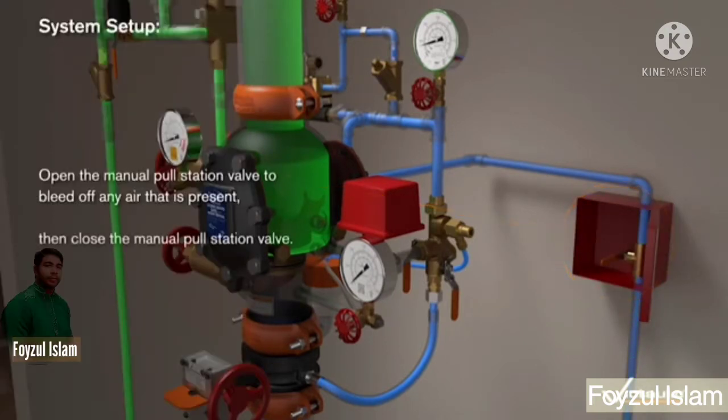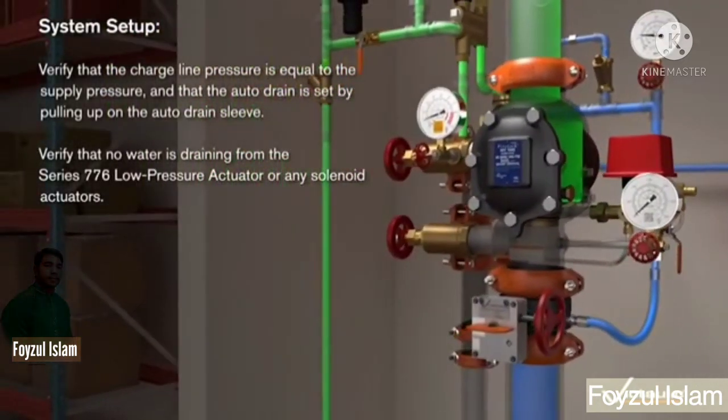Then in system setup, open the manual pull station valve to bleed off any air that is present, then close the manual pull station valve. In system setup, verify that the charge line pressure is equal to the supply pressure, and that the auto drain is set by pulling up on the auto drain sleeve.